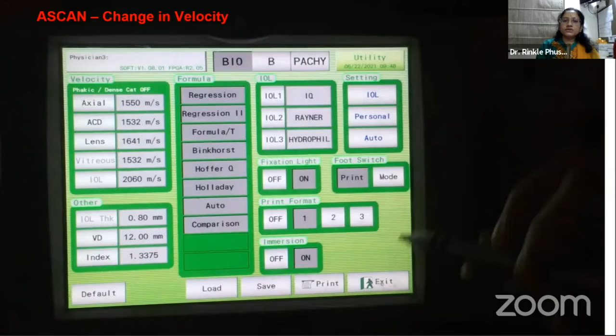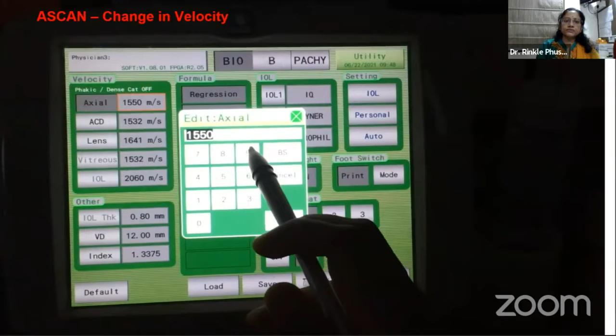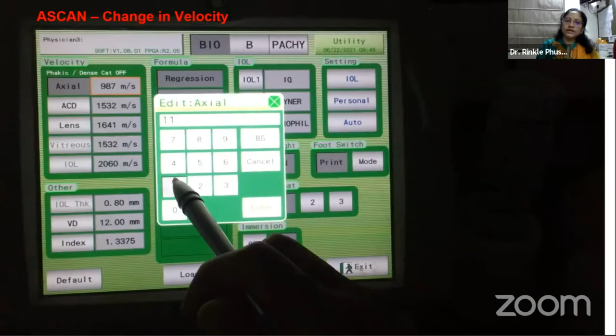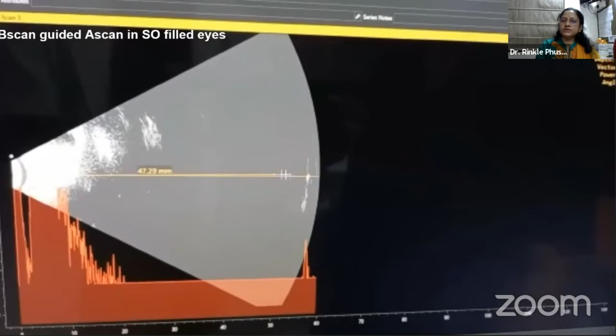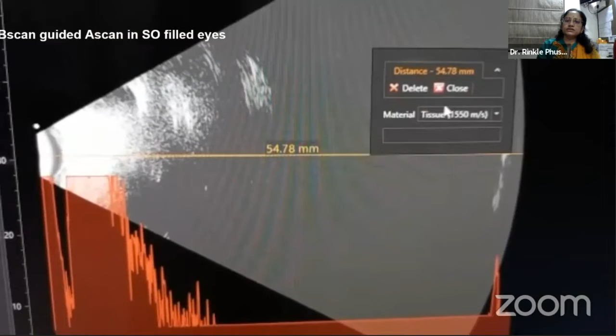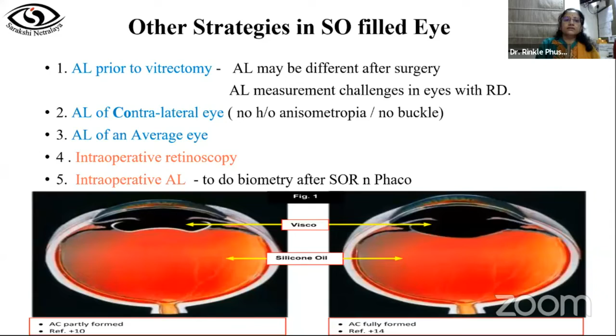Just to show how to change the velocity on the A scan, you change the velocity from 1550, which is standard, to 987 for 1000 centistokes of silicone oil and 1133 for 1300 centistokes of silicone oil. On B scan, you measure the axial length and then change the medium of tissue to silicone oil, and the machine gives you the calculation. If not, use the formula that we have previously discussed.